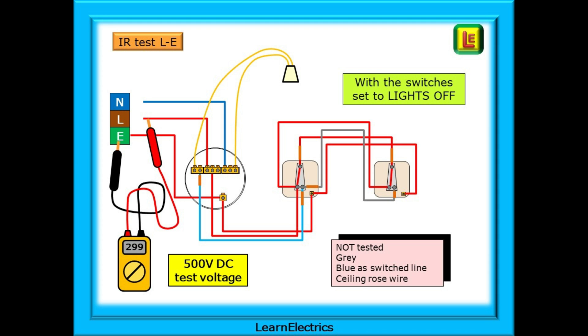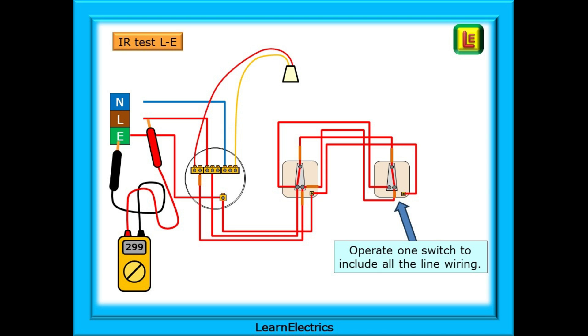The link that we used for the lower ohms tests must be removed. In this drawing, the switches have been set so that the lights would be off. Testing between the line conductor and the earth bar, you can see that not all the circuit wiring is red. This means that some parts of the wiring have not been tested. The grey wire, the blue conductor used as a switched line and the ceiling rose wires. This is not acceptable. We need to do more to include all the wiring. If we operate any light switch, we will effectively put the switches into the lights on position. Now we've included all the wiring in the circuit except the neutral from the consumer unit and the neutral to the light pendant. But we will get to this. A reading of 299 mega ohms is a pass on my meter.